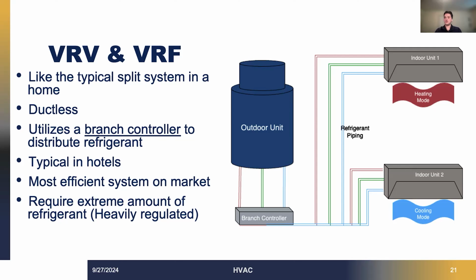And as you can see in the image, there is an outdoor unit which is then connected to a branch controller, and this branch controller is kind of the brain of the VRV and VRF system. Then it splits out and goes to the indoor units, and those are those wall cassettes that you might see in a hotel. Different rooms, rooms right next to each other, could be in heating and cooling modes. Say one tenant wants the heating because of the night, and one is just very hot, so they can get the cooling mode.